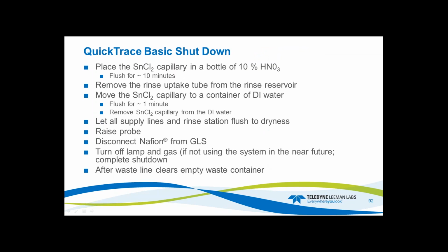You want to run your lines, flush your lines to dryness. Raise your probe through the Autosampler, disconnect the Nafion. Turn the lamp off. If you're not going to use the system, you can do a shutdown, but basically turn the lamp off and then turn your gas off at the tank, and then it's ready for the next day. And again, empty your waste container.